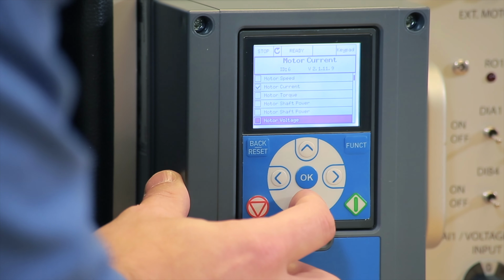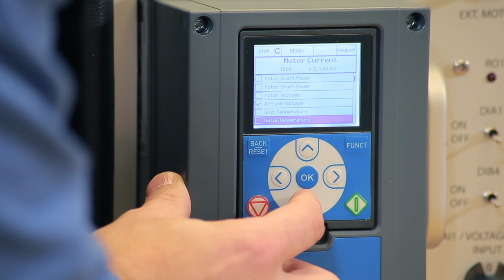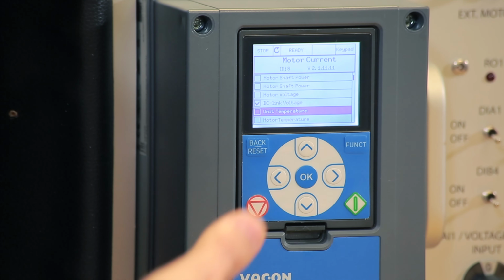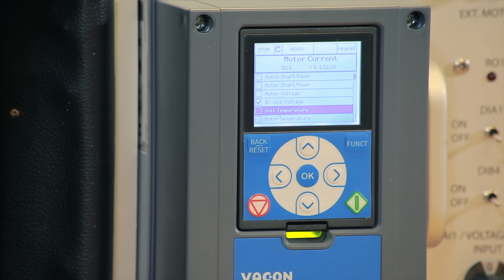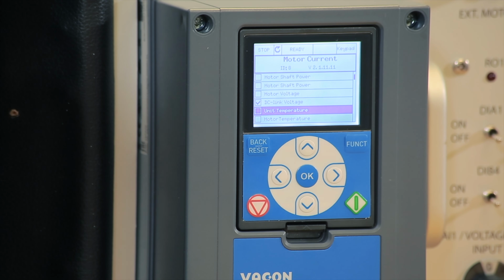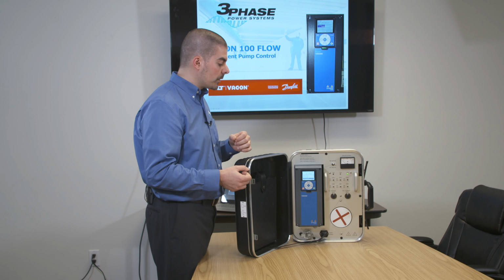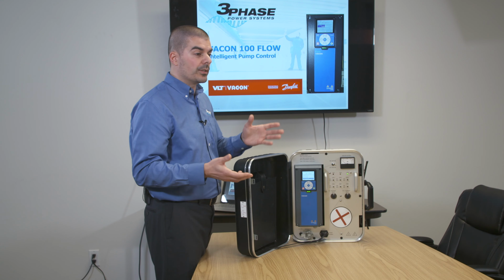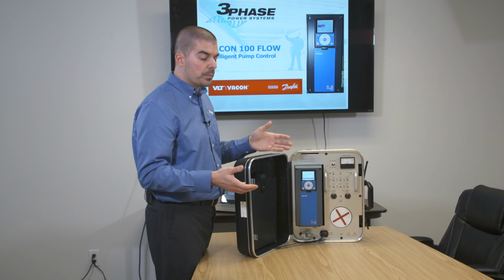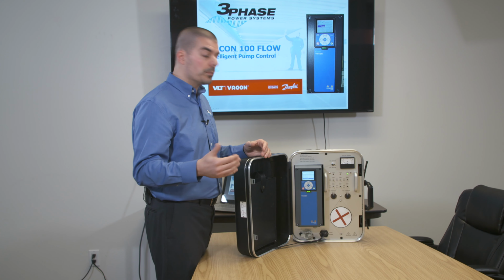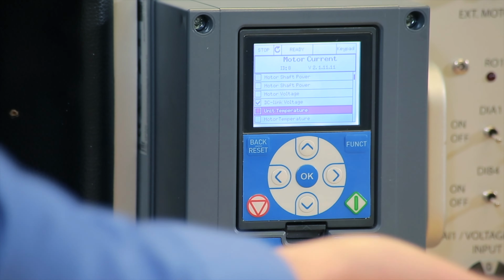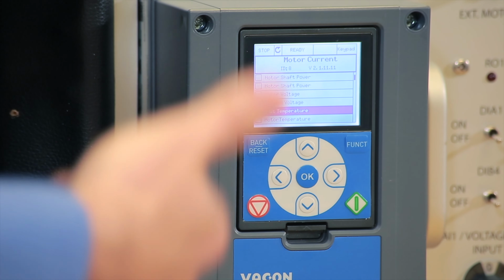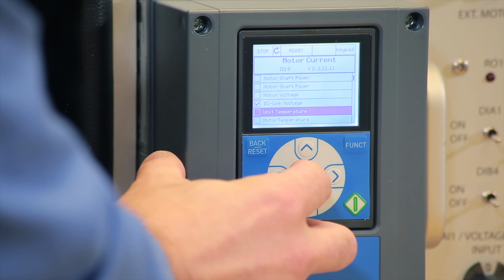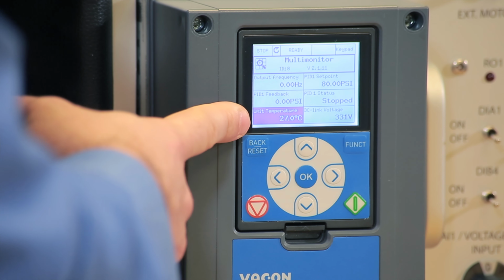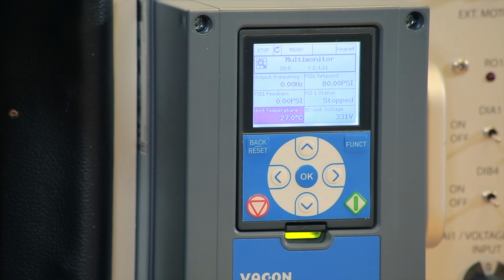For example, right now, we can monitor unit temperature. You can monitor any number of different things: errors, flushing status, reversing status. For example, auto cleaning, deragging, if the pump allows you to go backwards and forwards to dislodge the impeller. But right now, the one we're going to pick to show you how to change it on the multi-monitor is unit temperature. So we click OK, and it gives you the actual temperature of the drive itself, 27 degrees Celsius. So this is an example of how you can change this.